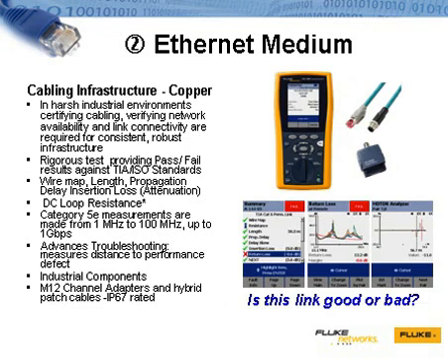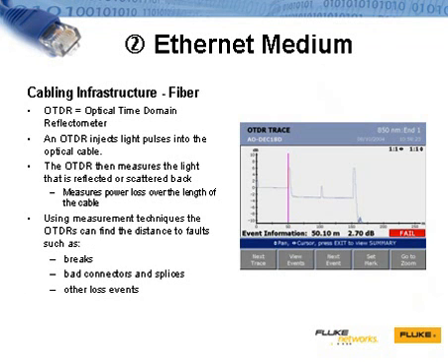The same TDR-type functionality can be used over fiber with an OTDR. Over fiber, the result is a signal loss over distance graphical representation called a trace. This is a single-ended test, so you're not required to know where the other end of the fiber is to get an idea of where a problem may be.